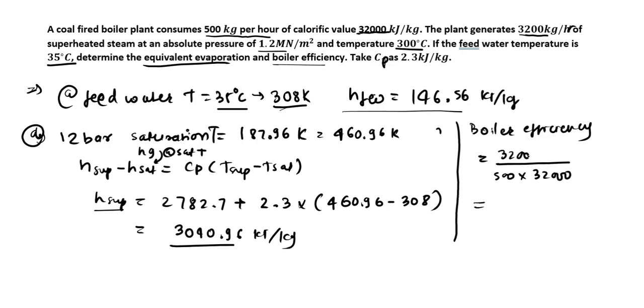So that will be 3200 kg per hour of steam into the specific enthalpy of the steam, which will be H minus H feed water. Because that is how much energy the steam is having or outputting. So this is how much work the boiler is doing. Firstly the enthalpy was H feed water and then the enthalpy became this H. So how much work the boiler is putting into the water can be observed from the upper down. So let us calculate this.